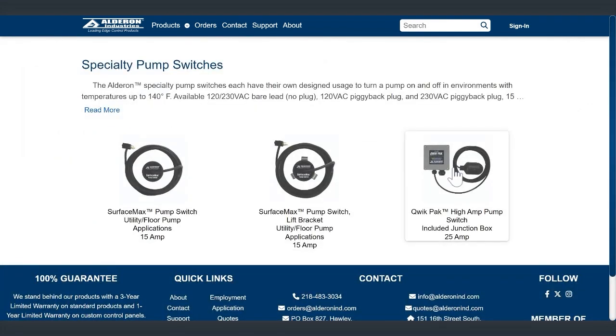And then we have our Qwik Pak, which is a control switch mounted to a control box, a junction box basically, with a power relay in there. So now we can handle up to 25 amps for a pump control. In the future, we are also going to have a 20 amp piggyback for our pump switches available. That's what these would look like. You got the different NEMA type cord set. This is our current 230 volt, current 120 volt, and we'll have a 20 amp version as well.